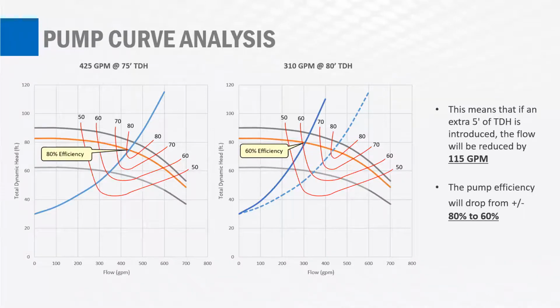This can pose some problems, of course. Not only do you see the drop in efficiency that might lead to higher power costs, but with the lower flows, you may have some serious problems with that. That could cause sanitary sewer overflows because the pump is simply not delivering what it's supposed to.